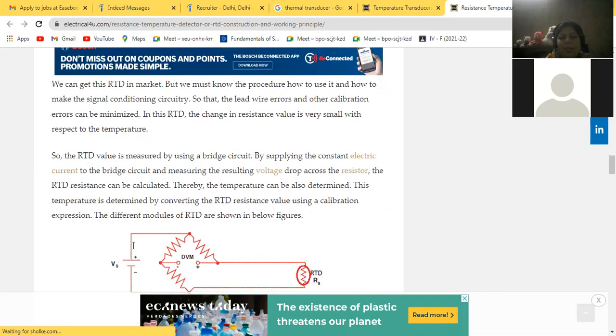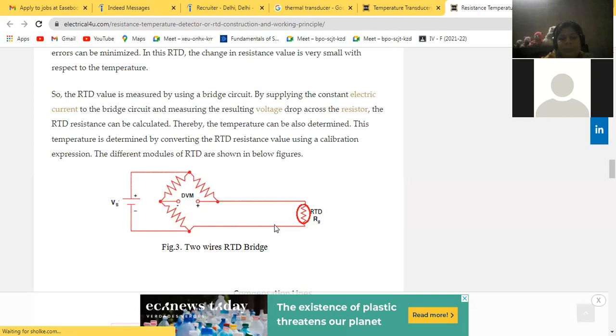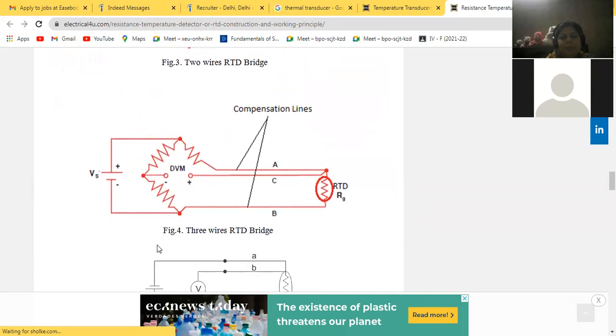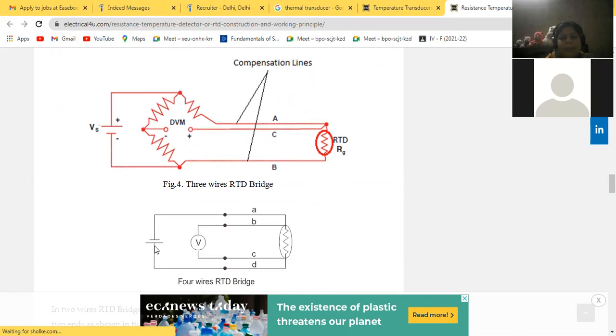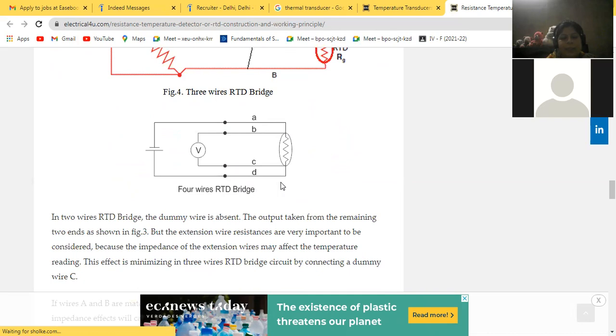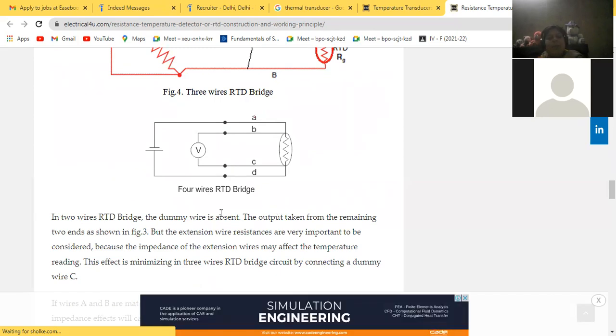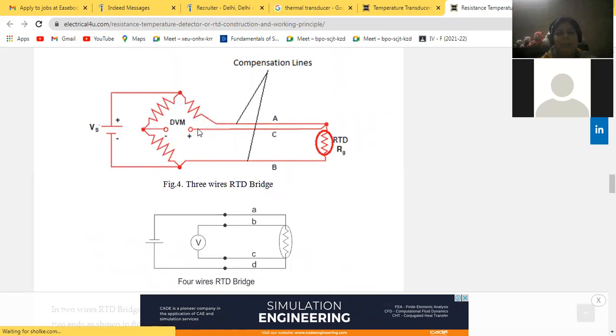The different modules of RTD are given below. You can see here the two wires of the RTD bridge. These are the three wires, A, B, and C. These are the four, A, B, C, D. Now in the two wire RTD bridge, the dummy wire is absent. The output is taken from the remaining two ends as shown in the figure, but the extension wire resistances are very important to be considered because the impedance of the extension wires may affect the temperature reading. This effect is minimized in the three wire RTD bridge circuit by connecting a dummy wire C. You can see here.